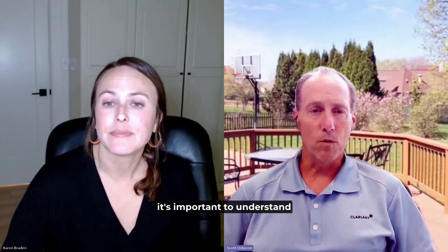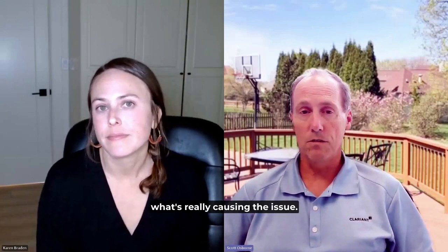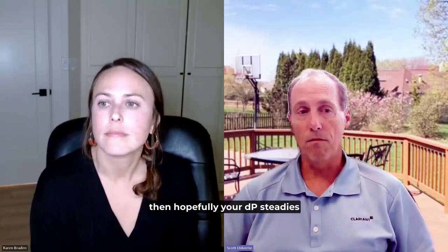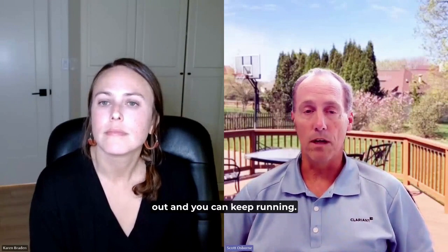Well, first off, it's important to understand what's really causing the issue. If you have an ongoing waste heat boiler leak, and you can confirm it, then you can expect DP is going to continue to rise. And if you fix the leak, then hopefully your DP steadies out and you can keep running.